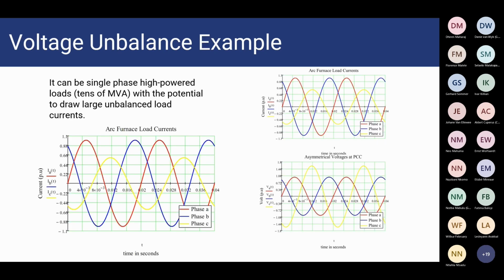Okay, an example of voltage unbalance. There we have a nice arc furnace as a load, an image of that. That load draws a very unbalanced current, as you can see on the waveform. And an unbalanced load like that will result in unbalanced voltage, as you can see on the bottom graph on the page as well. So arc furnaces are one example of a load that is common in causing a high voltage unbalance.